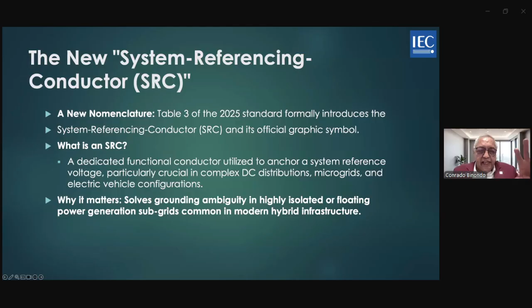For traditional AC systems, your design remains a grounded conductor neutral. However, when you draft complex single-line diagrams featuring a solar array, battery storage, and an EV charger sharing a common DC bus, you will designate the grounding reference line as the SRC. This simplifies labeling and prevents engineers from incorrectly using AC terms like neutral on a pure DC link. So that's clear now, the use of the SRC, that's why we highlighted it in the standards.